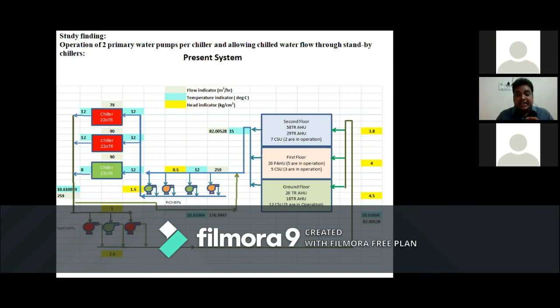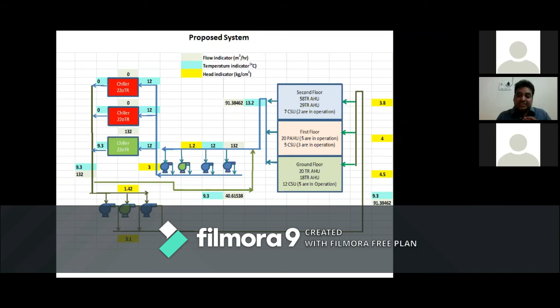The temperature was coming at around 10 degrees centigrade. When we checked it and closed these valves, the water is not going to this, and now the temperature is 9.3. So what is the saving achieved? You will be surprised with just 2 degrees centigrade, what change, what savings they can achieve.